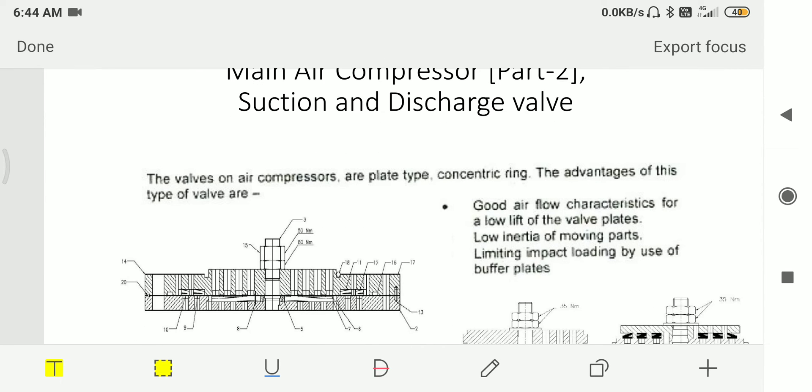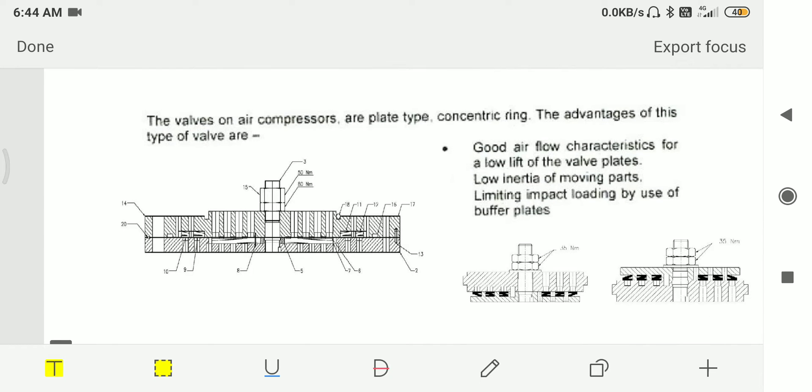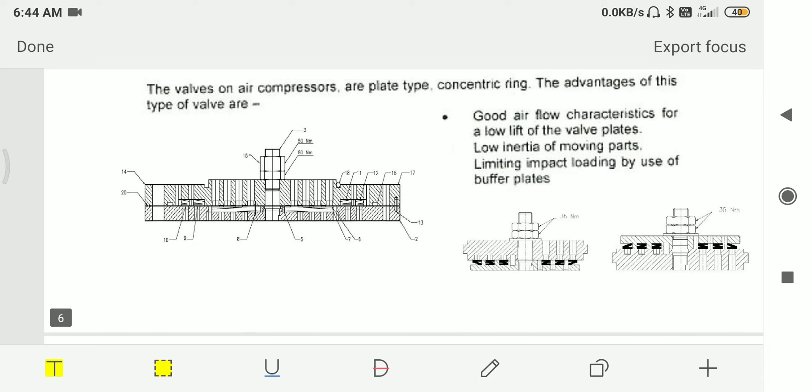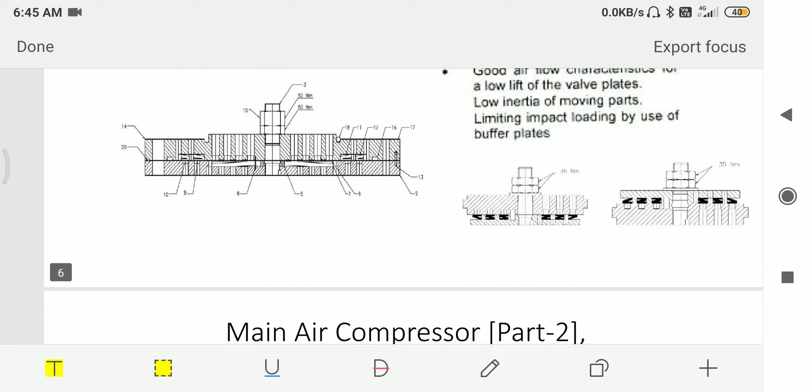Then we have suction and discharge valve. The valves on air compressors are plate type with concentric rings. Main advantages are good air flow characteristics for low lift of the valve plate, low inertia of the moving parts, and limited impact loading by use of buffer plates.